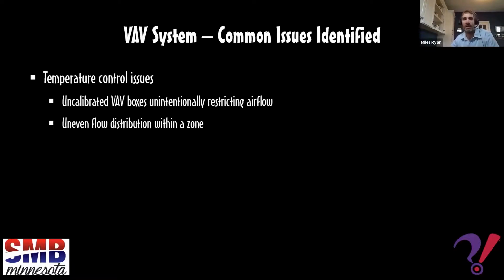Another problem would be uneven flow distribution within a thermal zone. On a project I was working on in a hospital about 2 years ago, there was a scan room for an MRI machine or something to that effect, and there was an equipment room just off of that. I was sitting in the equipment room, which they had been occupying and using for several weeks prior to me performing a commissioning process there. And I was just getting cold air dumped on me and I was freezing.